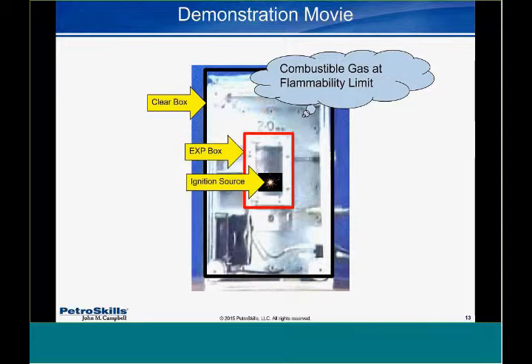The thing to notice is the gap between the faces on these explosion-proof fixtures. The reason the flanges are so wide is that they're used to quench the explosion, or the flame front. It works similar to a flame arrestor. The hot gases after the explosion in the box are cooled, and what you're trying to do is prevent the flame front from exiting the box into the surrounding cloud that has a larger mass of hydrocarbon, and thus prevent the explosion.